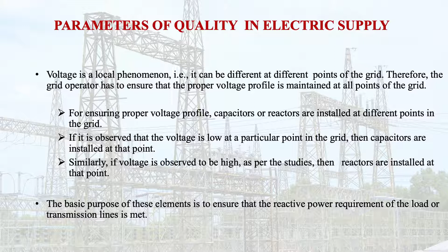When you learn more, you will come to know about all these aspects. Then similarly, if the voltage is observed to be high, as per the studies, then reactors are installed at that point. So the basic purpose of these reactive or capacitive elements is to ensure that the reactive power requirement of the load or transmission line is met. This reactive power is needed whenever we connect large inductive machines, such as transformers and big motors, which need it for generating the magnetic field. So this should be met by these elements to save our lines or power supply system.